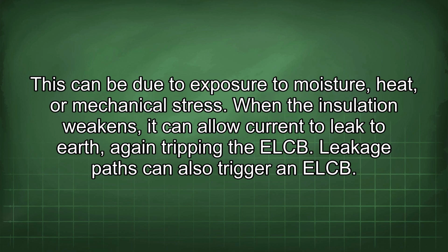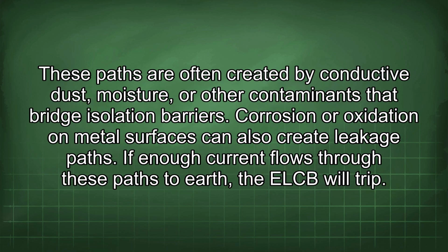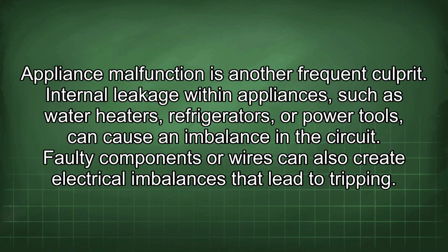Leakage paths can also trigger an ELCB. These paths are often created by conductive dust, moisture, or other contaminants that bridge isolation barriers. Corrosion or oxidation on metal surfaces can also create leakage paths. If enough current flows through these paths to earth, the ELCB will trip. Appliance malfunction is another frequent culprit. Internal leakage within appliances, such as water heaters, refrigerators, or power tools, can cause an imbalance in the circuit. Faulty components or wires can also create electrical imbalances that lead to tripping.